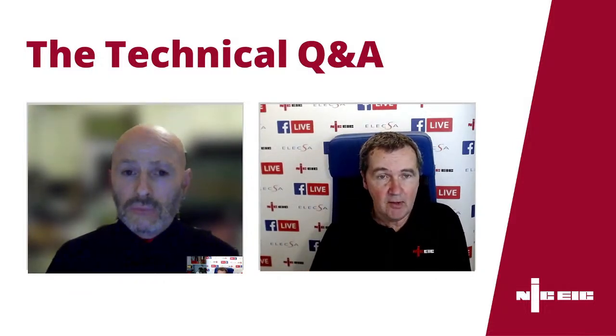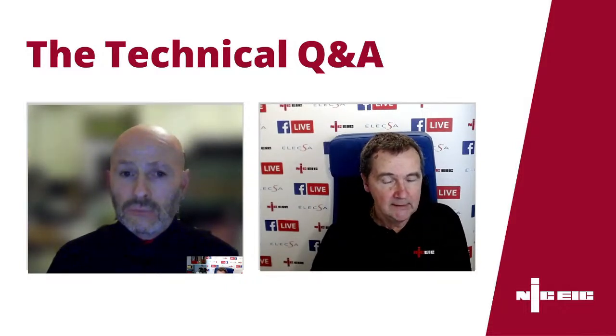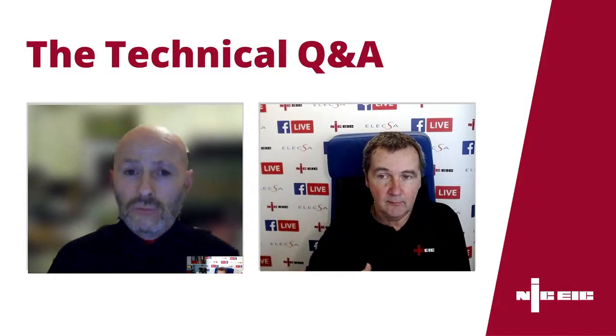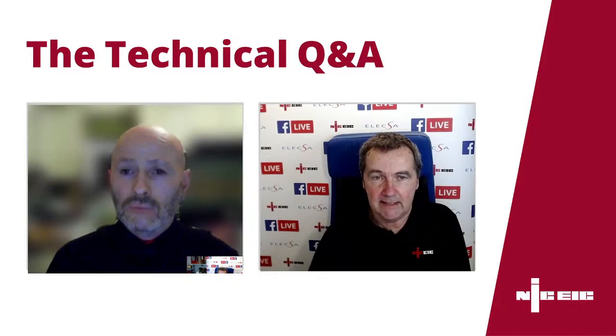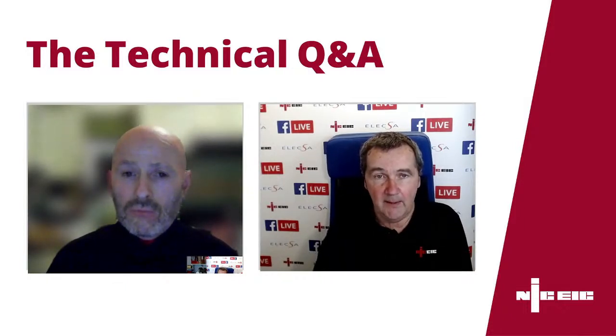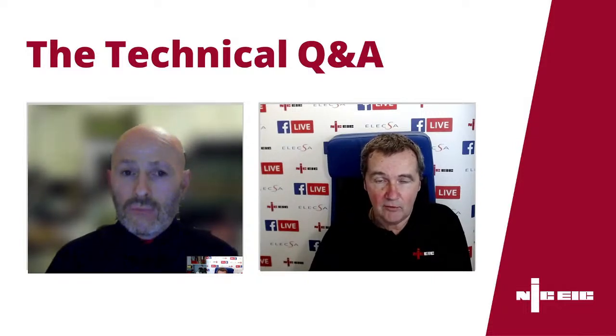So don't be surprised sometimes if it's only slightly higher. The DNO may not even consider that worth coming out, but we always recommend recording it and reporting it. Then at a later date, if you can see it's slowly increasing, make that comment also to the DNO, because that could be an indication of a problem with the cabling in either the transmission or distribution side of the business. If it's continually getting greater year on year, make them aware of that too.